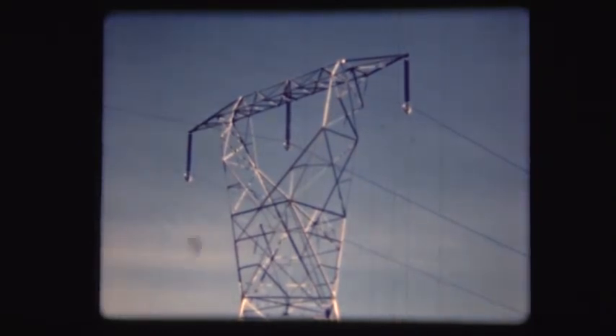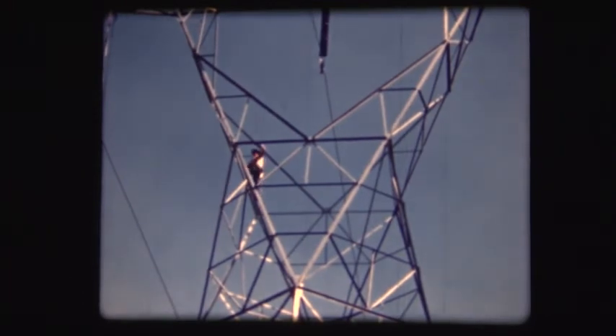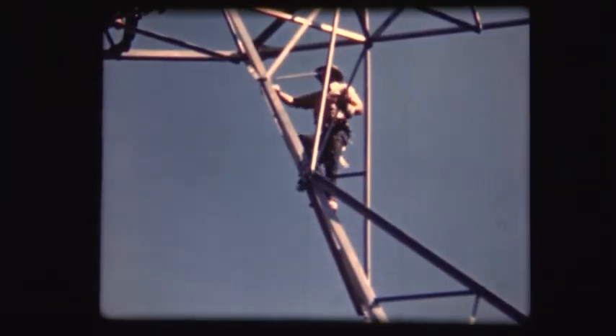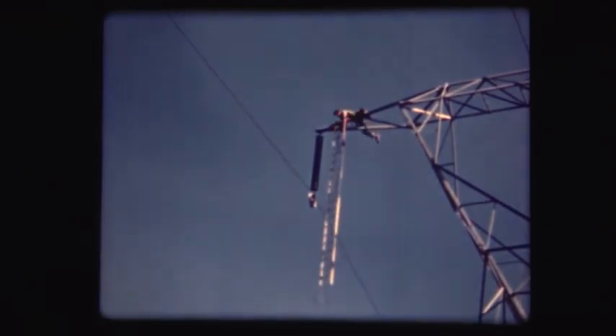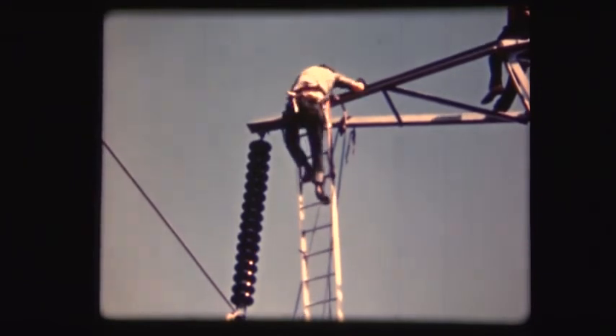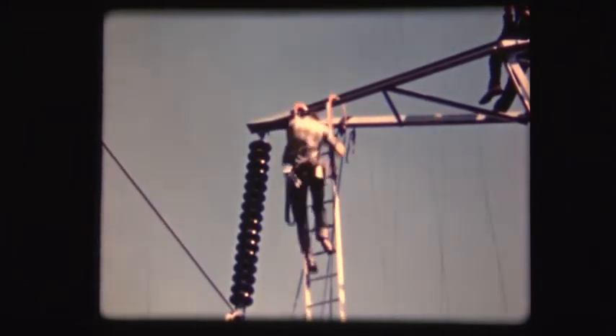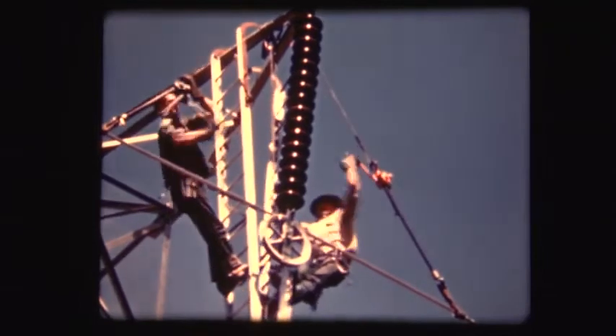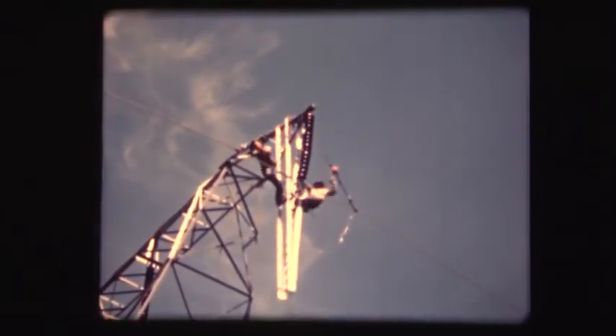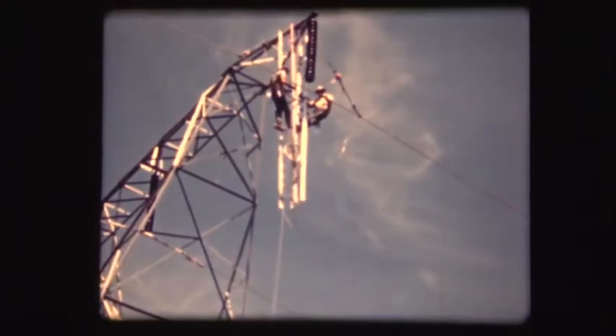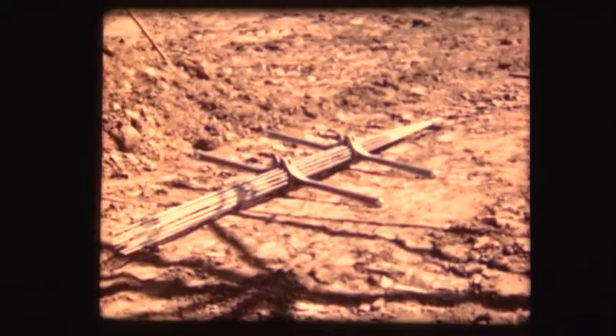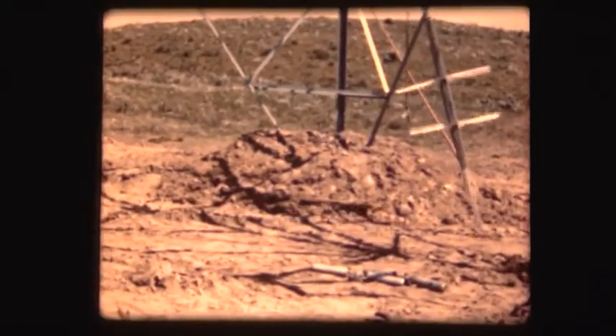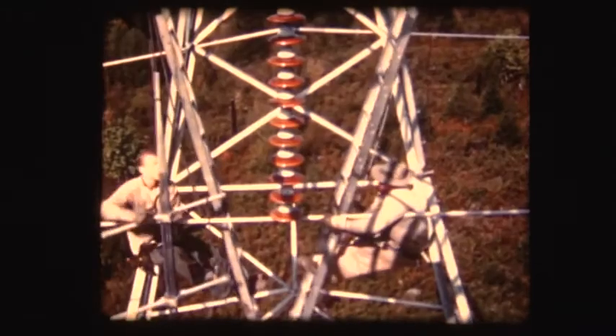The next job is clipping, removing the conductor from the sheaves and attaching it to the insulator. This is one of the most spectacular jobs in transmission line construction. Line men must do their work on ladders suspended in mid-air, often a hundred feet or more above the ground. Hand-operated hoists are used to lift the conductor from the sheave. The sheave is lowered, and bundles of tapered armor rod, which have already been assembled on the ground, are hoisted and placed around the conductor.